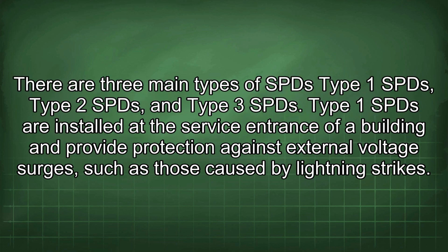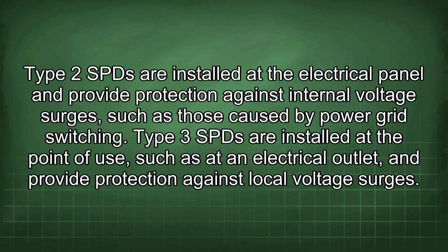There are three main types of SPD: Type 1, Type 2, and Type 3. Type 1 SPDs are installed at the service entrance of a building and provide protection against external voltage surges, such as those caused by lightning strikes. Type 2 SPDs are installed at the electrical panel and provide protection against internal voltage surges, such as those caused by power grid switching. Type 3 SPDs are installed at the point of use, such as at an electrical outlet, and provide protection against local voltage surges.